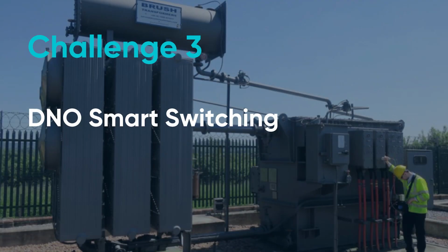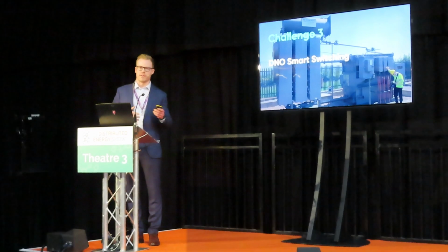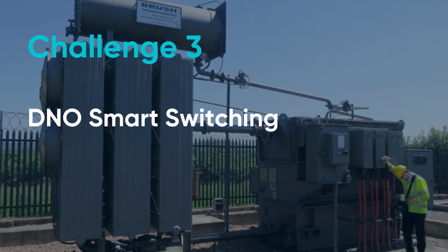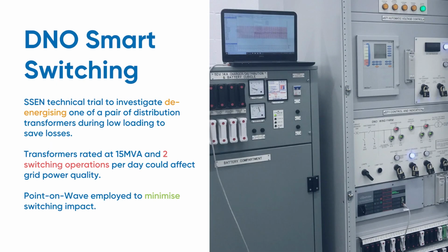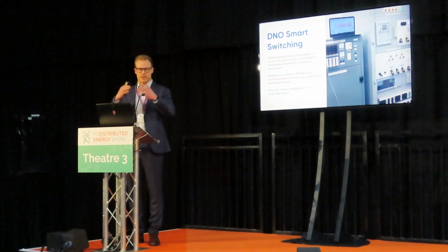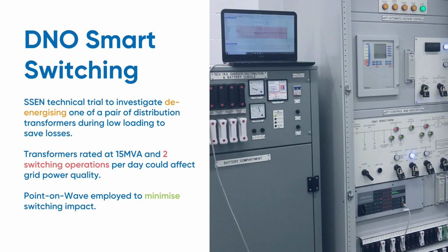Challenge number 3, this one's a little bit unique. It wasn't coming from the customer's renewable generation side, and it wasn't coming solely from the network side for a black start scenario. So SSEN, we're looking at initiatives here to help with distribution transformer losses. What you have typically in a 33 kV distribution network is you'll have 2 parallel transformers, and they'll be feeding a town or a certain area of network at lower voltage. Obviously, at peak times in the morning and in the evening, we do need both of those transformers because of the power that's going through them.